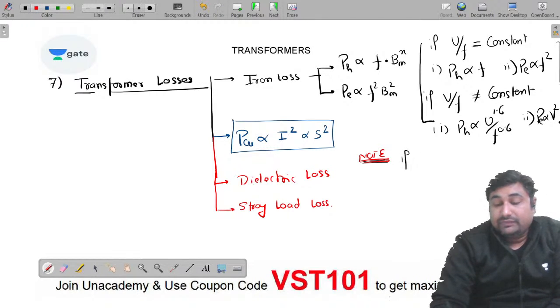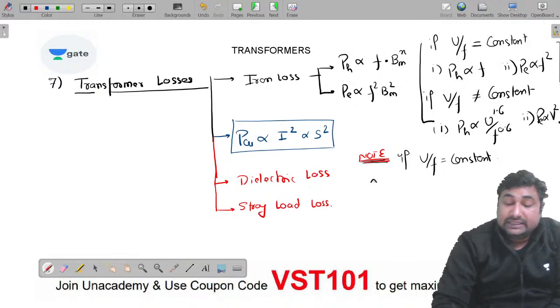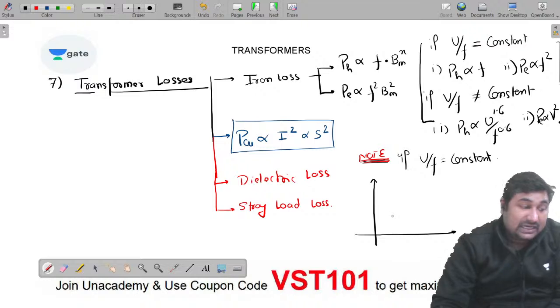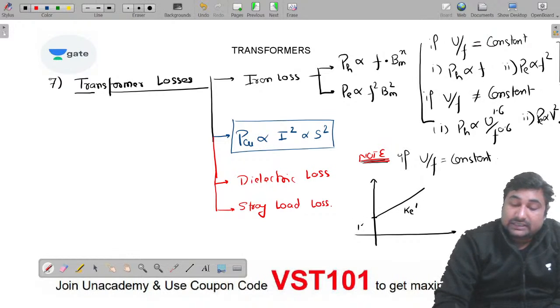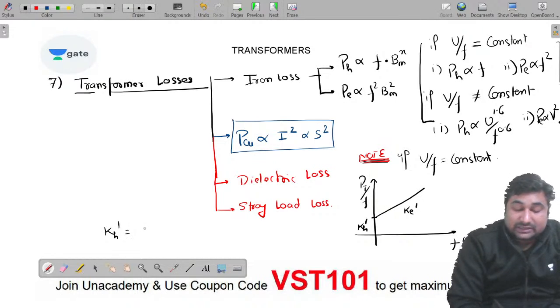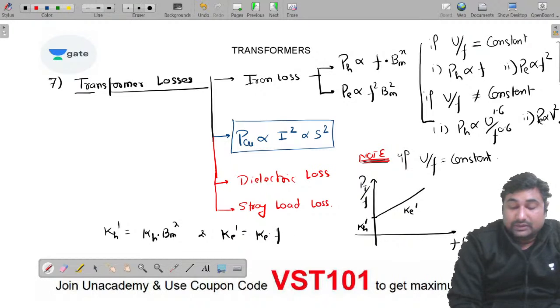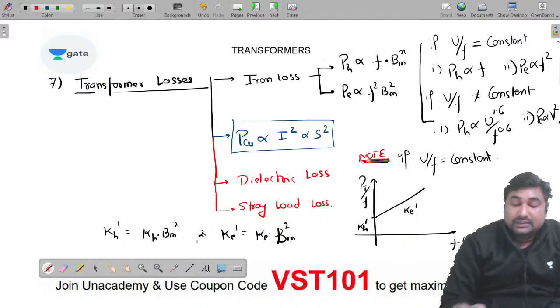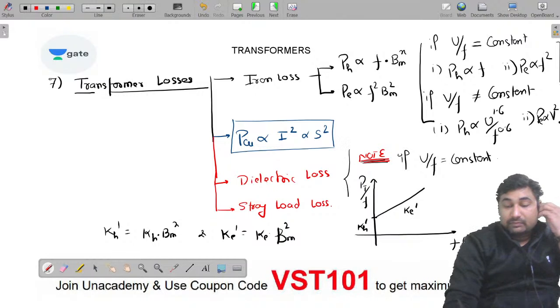Please observe, if V by F ratio is constant, then always remember about this straight line. The slope of this straight line is Ke dash, the constant is Kh dash, and this is your watt per hertz. So this straight line, where Kh dash is nothing but Kh into Bm to the power x, and Ke dash is Ke into Bm to the power 2. In that way you can also solve numericals.